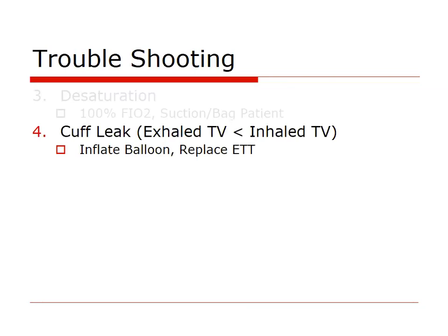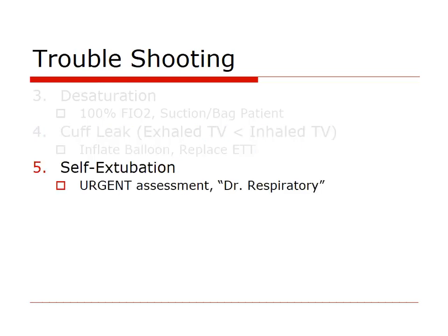When it comes time to extubate, we purposely deflate the cuff to make sure there's a cuff leak, but that's during weaning. The rest of the time, you don't want a leaky cuff. How would you know you have one? If the machine is programmed to deliver 450 cc's but the reported exhaled tidal volume is only 200 cc's, that implies a leaky cuff. Best thing to do is ask respiratory to come see the patient—they'll first put more air into the balloon to see if that fixes it. If not, you have to replace the endotracheal tube, since the balloons sometimes just lose their structure.